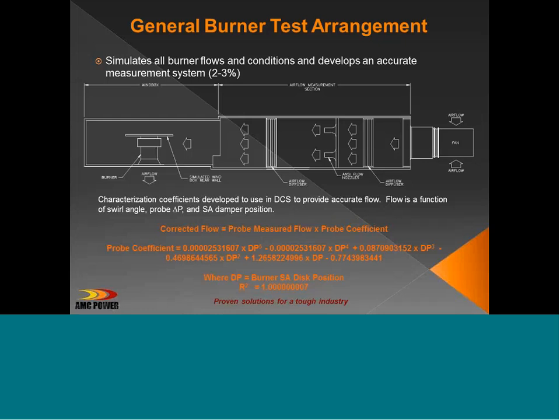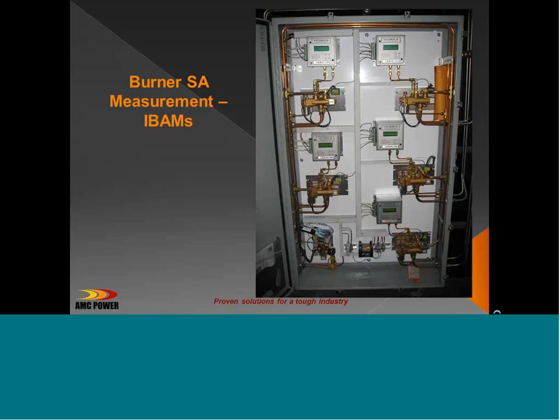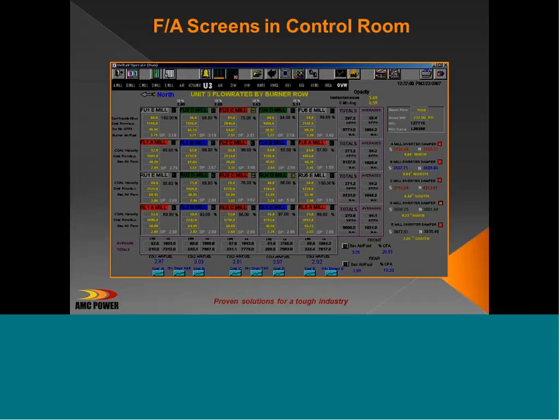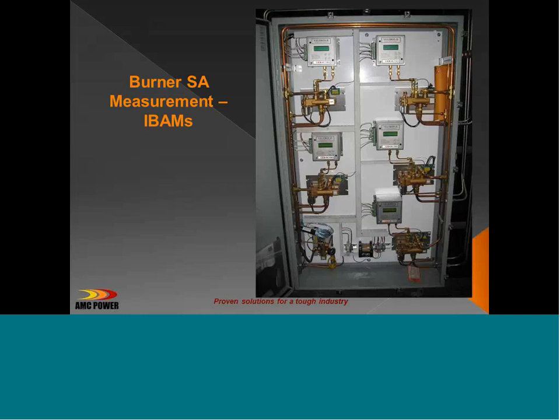We're looking at the general burner test arrangement here, right? Another important feature that we use when we're measuring flow, of course, we're using a pitot tube. As with all of our pitot measurements, we have a transmitter that's looking at the DP and transmitting the signal back to the DCS to use for the mass flow measurement. These are purge valves. We also want to make sure that the pitot tubes stay clean. So as with everything we do, primary airflow, secondary airflow, overfire airflow, and burner airflow, there's a series of valves that are used to blow the pitot tubes back once a day.